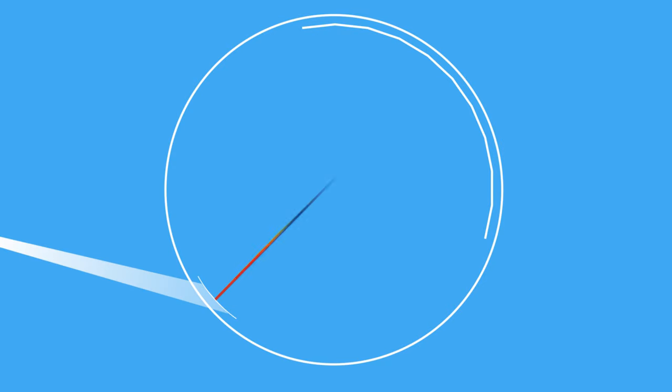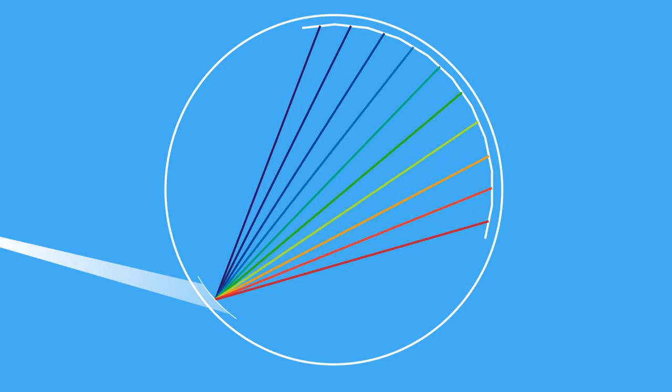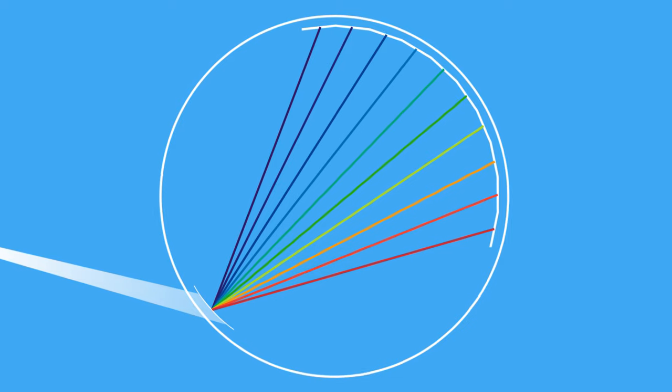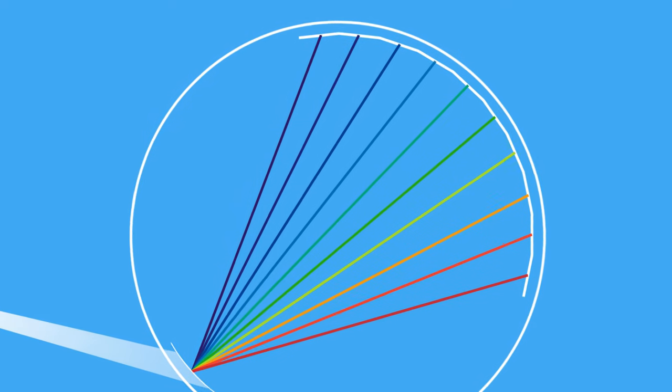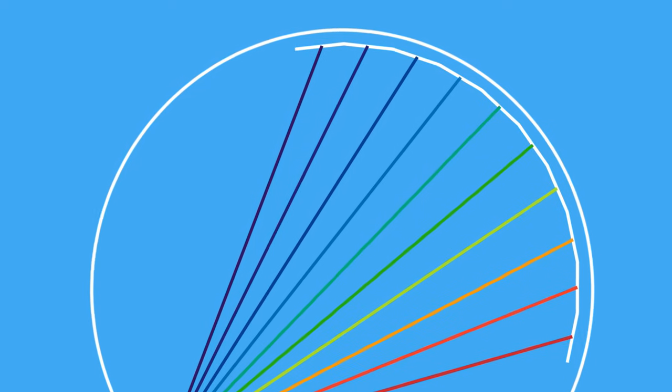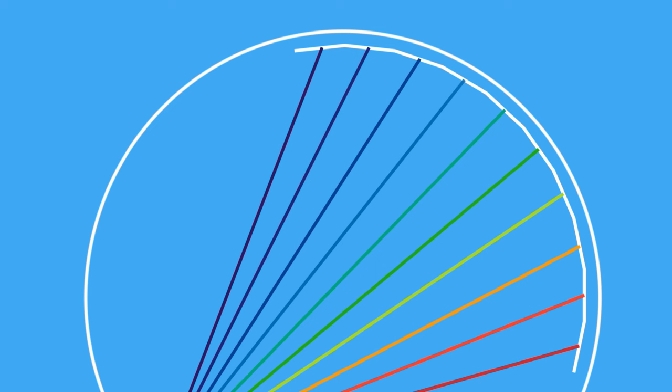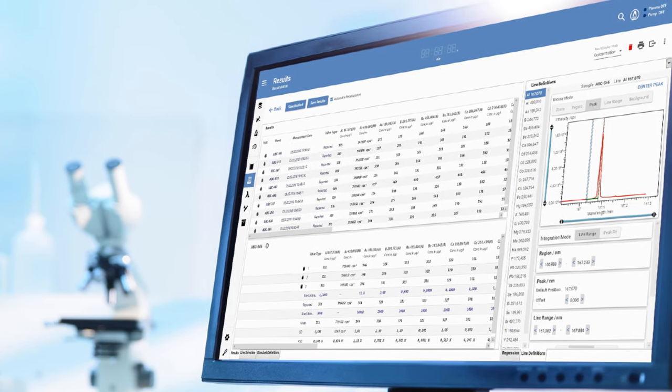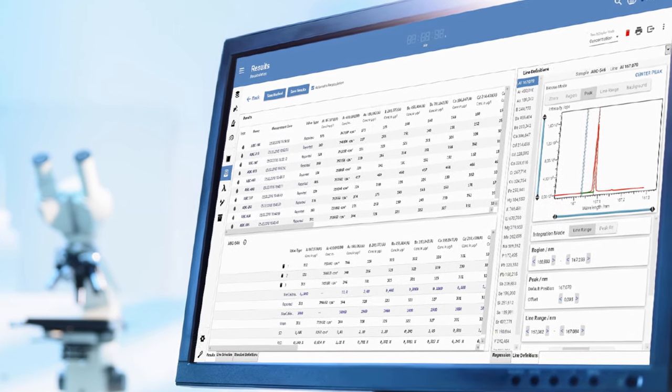The light is transferred into the high resolution, no-purge sealed optical system, which separates the light into the specific wavelengths for the elements to be measured. As these wavelengths strike the detector array, light intensities for each different wavelength are quantified and sophisticated software converts them into concentration units.